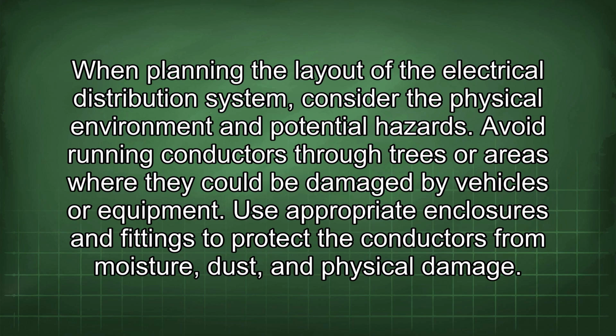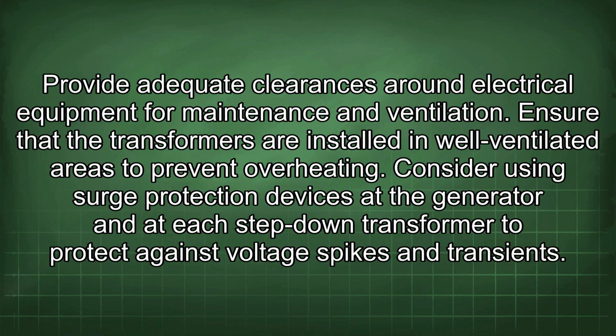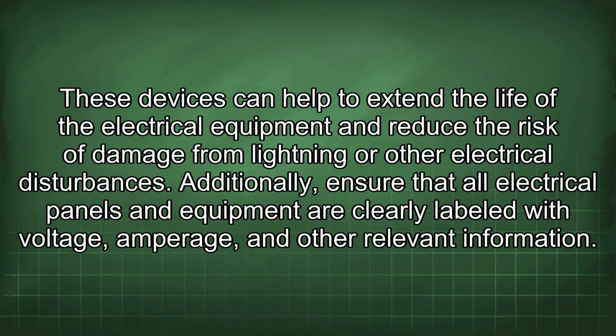Use appropriate enclosures and fittings to protect the conductors from moisture, dust, and physical damage. Provide adequate clearances around electrical equipment for maintenance and ventilation. Ensure that the transformers are installed in well-ventilated areas to prevent overheating. Consider using surge protection devices at the generator and at each step-down transformer to protect against voltage spikes and transients. These devices can help to extend the life of the electrical equipment and reduce the risk of damage from lightning or other electrical disturbances.